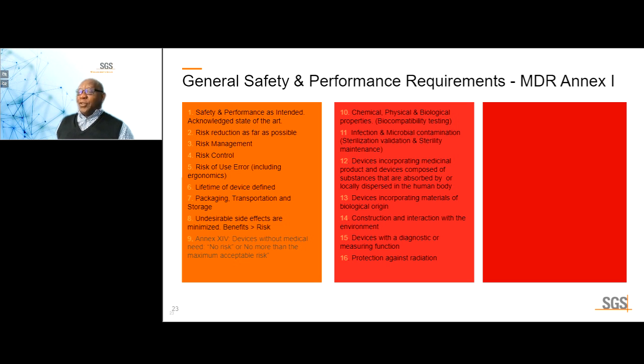GSPR 11 that talks to infection and microbial contamination covers sterilization, validation, and sterility maintenance. Believe it or not, has 8 subsections. For instance, subparagraph 11.1 goes from A to D. So this is why you must pay attention to every line item and, if applicable, provide evidence to demonstrate compliance.